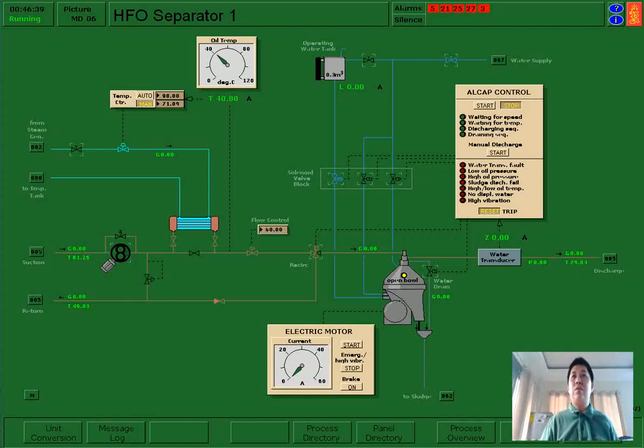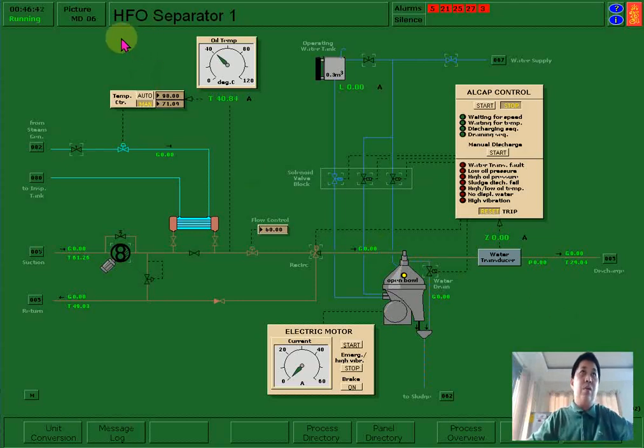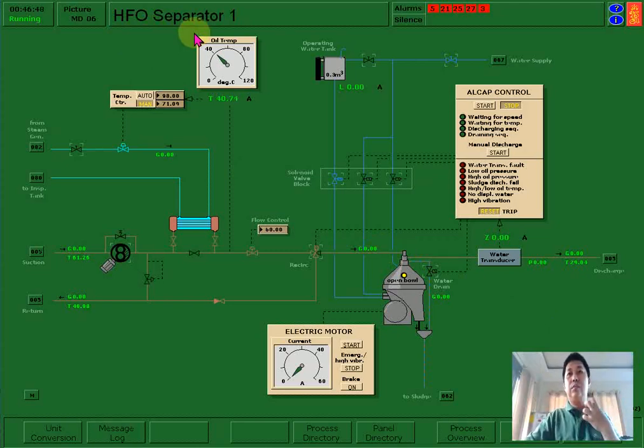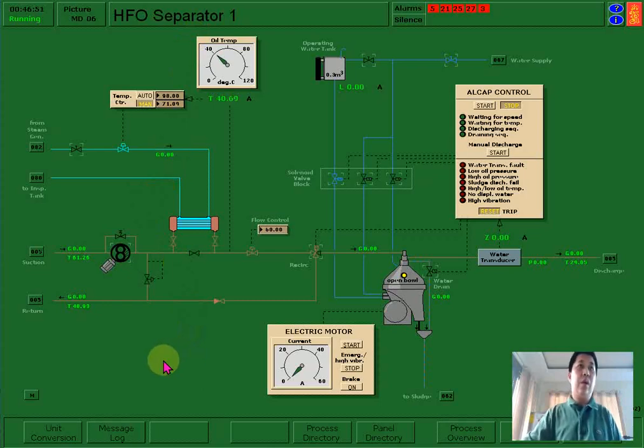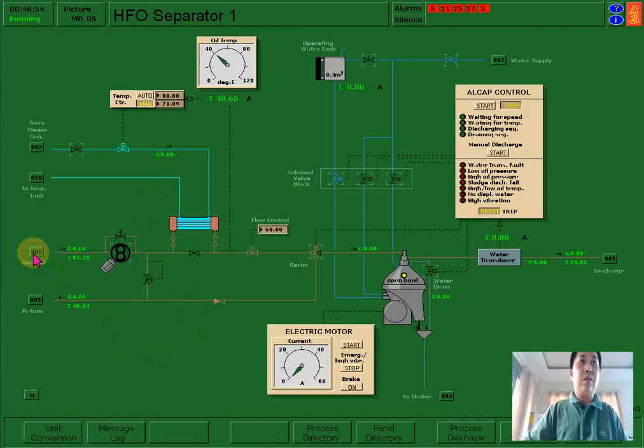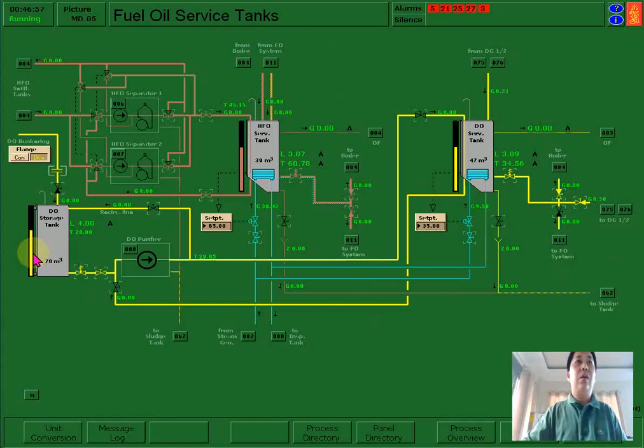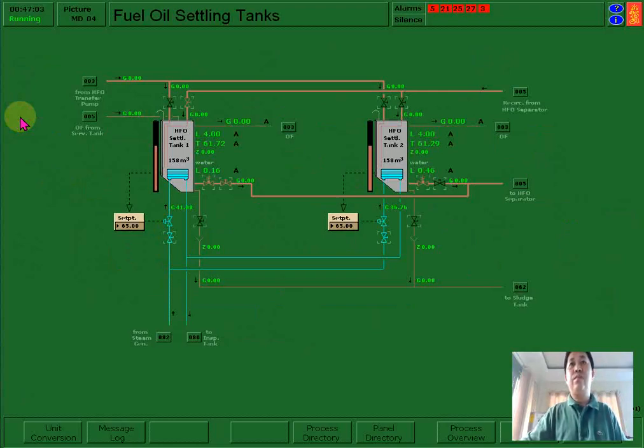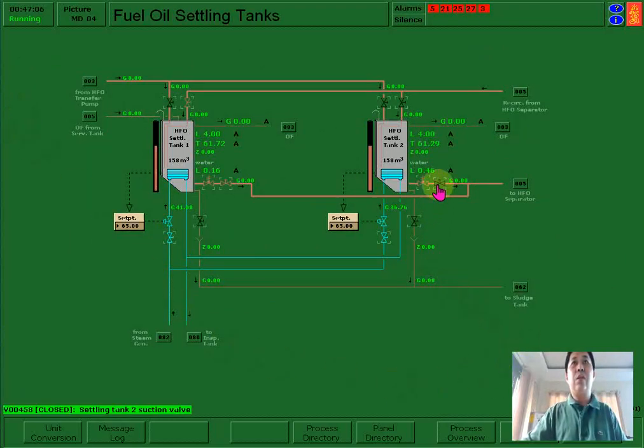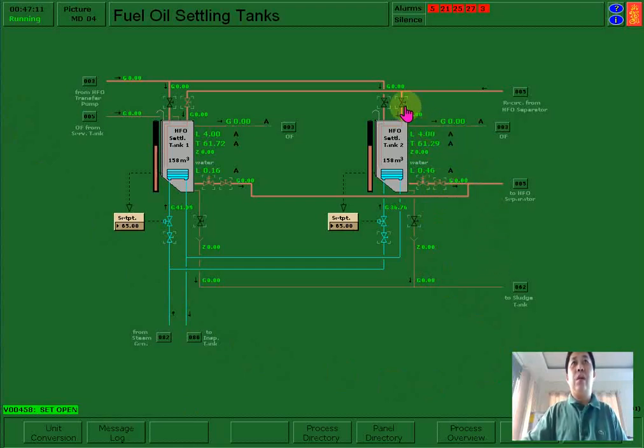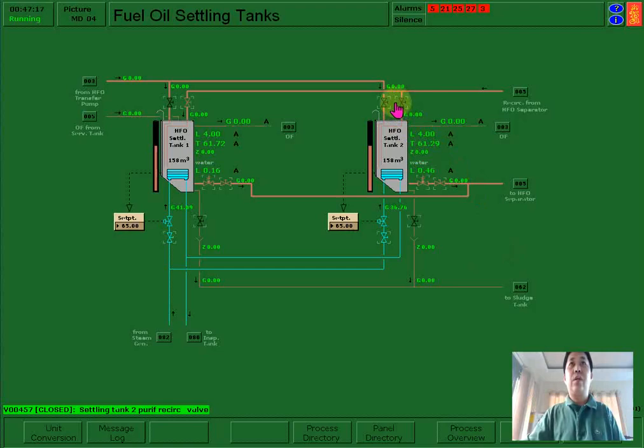First I have to start the fuel oil purifier number one, the HFO separator number one. I have to open the suction line from the settling tank. This is your suction line of your settling tank. The return line — no need to open because there is a circulation in your feed pump. So no need to open, only the suction line. Then let us proceed to the separator.